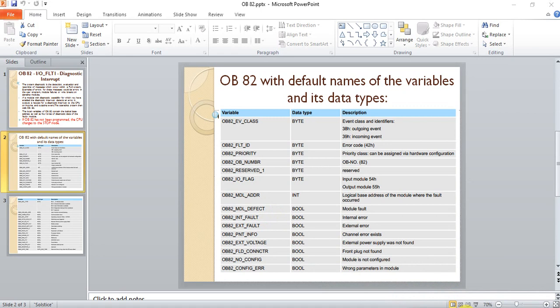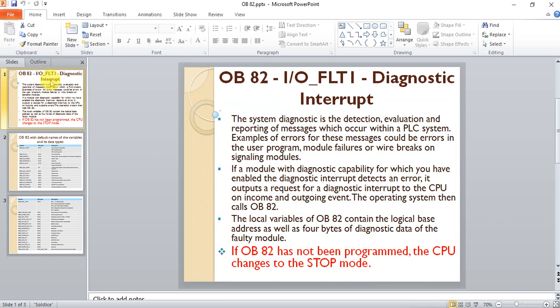Hello again. In this video we cover OB82, which is used for troubleshooting. OB82 is the IO fault or input/output module fault organization block, also called a diagnostic interrupt. OB82 is triggered when there is a fault on an IO module, such as wire breakage, power failure, and many other errors on the input/output module.